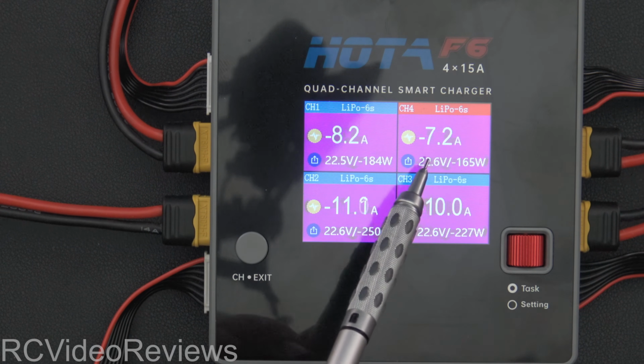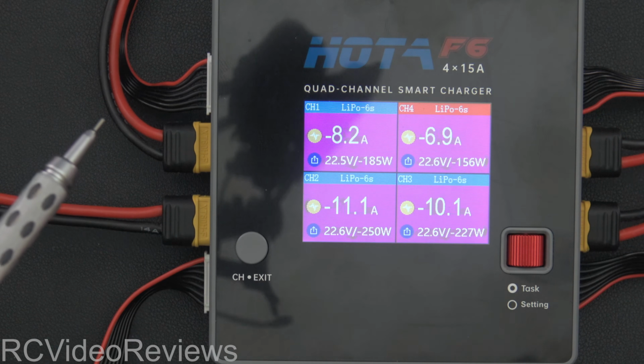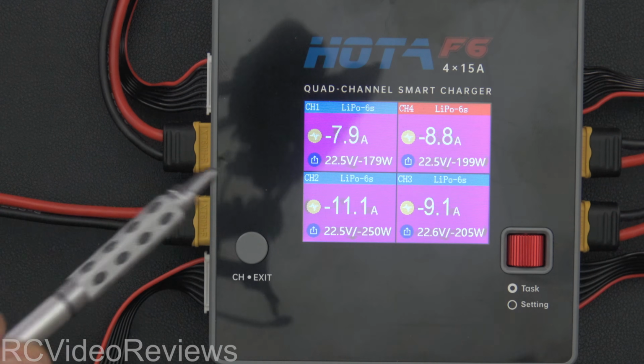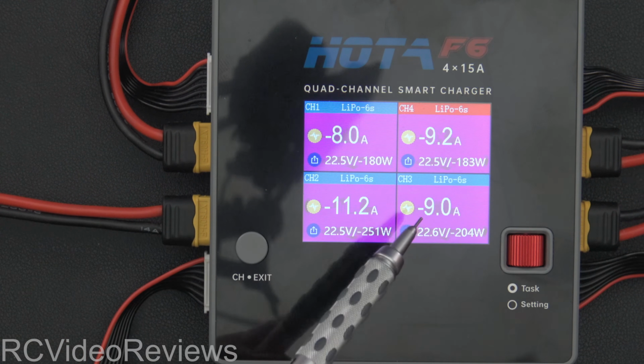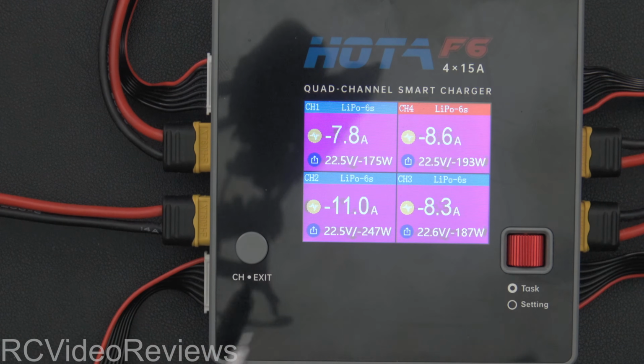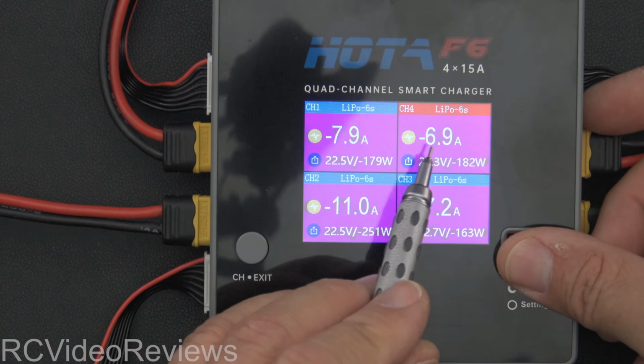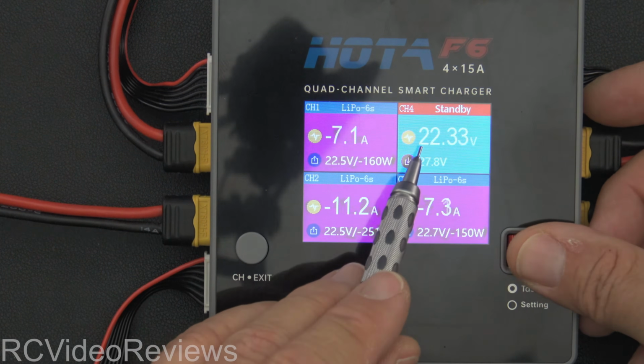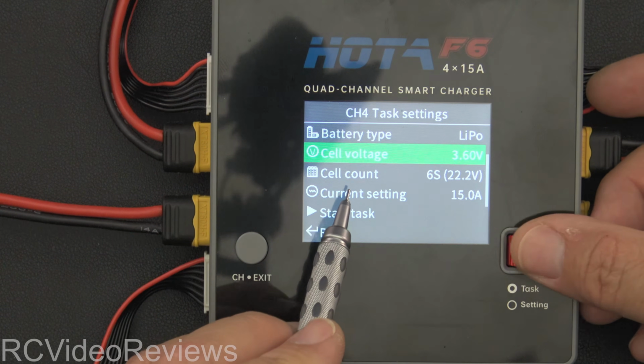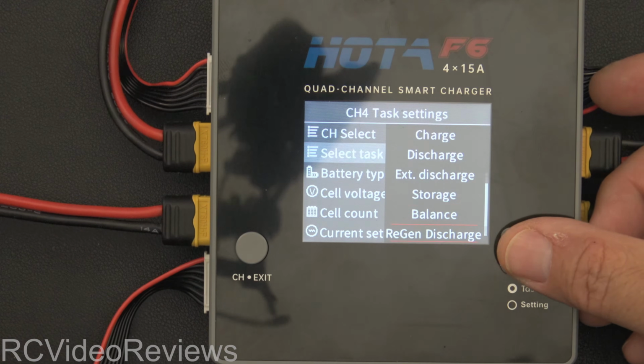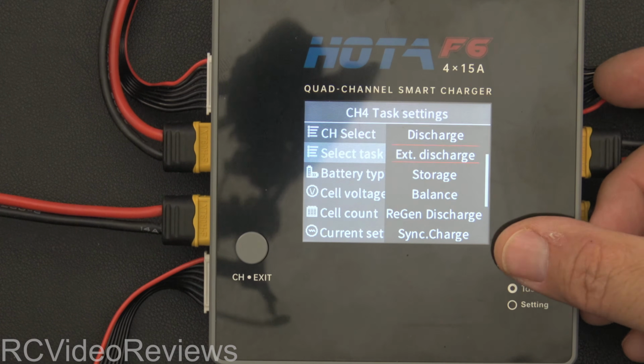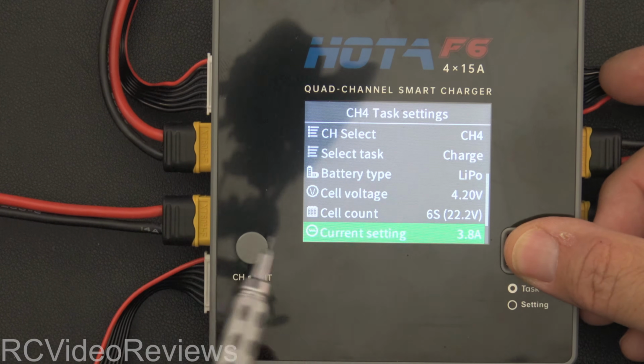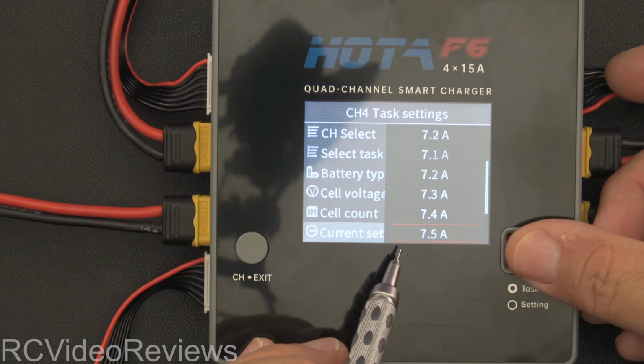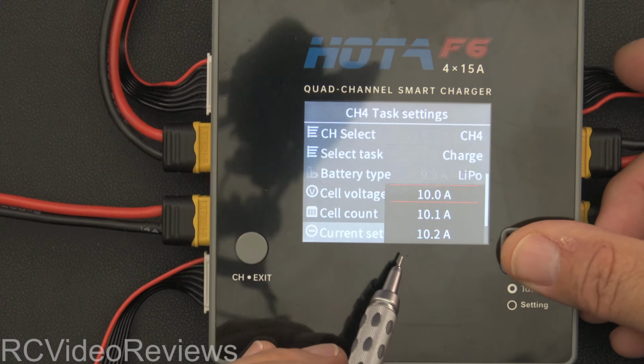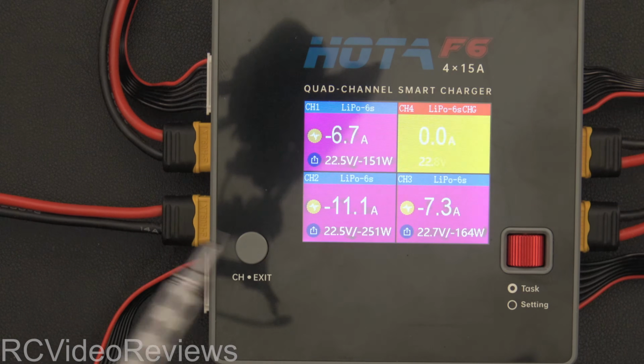Yeah, it's possible it was already just a little bit too close, but there you go. Now it's starting to climb up there. So that's pretty cool because we're dumping, that's what, 36, 37 amps into my battery bank right there. So pretty nice, right? That's a pretty cool functionality. And by the way, if we stop this one, we can change this task to a charge. They're independent channels is the bottom line. So what I'll do is I'll just set this one to charge if I can figure out how to do that. We'll leave it, it says 3.8. We'll bring it up to 10. And then we'll hit start.